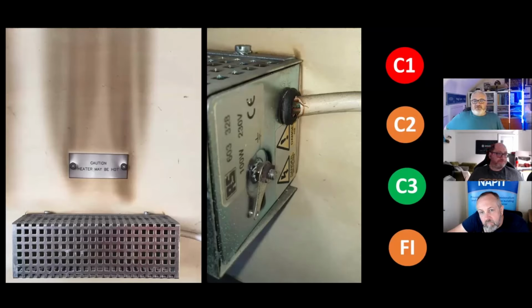But the picture on the right is the same one, because upon investigation, if you can see there's a little rubber grommet built into it, and it had basically cooked the cables. The cables were completely brittle inside - you can actually see, look, cracked, the copper in there. They're cracked, yeah, they are cooked. And there was no thermostatic control on that whatsoever, because the thermostat in the cupboard had been turned all the way up and was just baking and baking and baking.